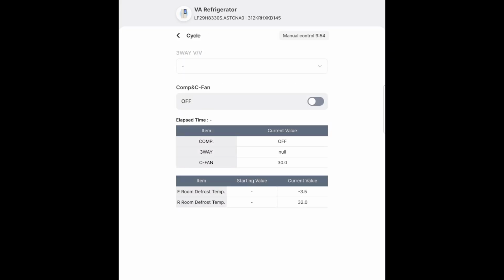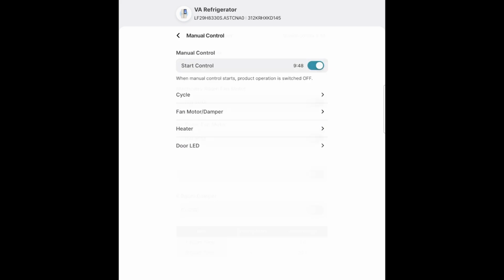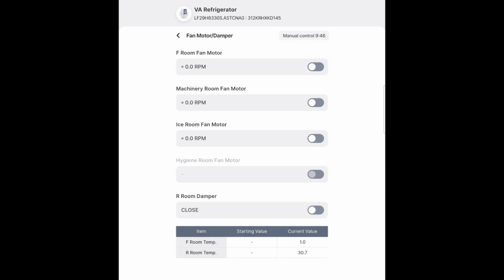If you hit cycle and turn that on, that's going to run the compressor and the condenser fan. We'll go to fan motor - let's say we want to turn on our freezer fan. I'm going to hit that button, and if the fan is working, you should see the RPM start to increase. It gave a green signal letting you know that fan is working.